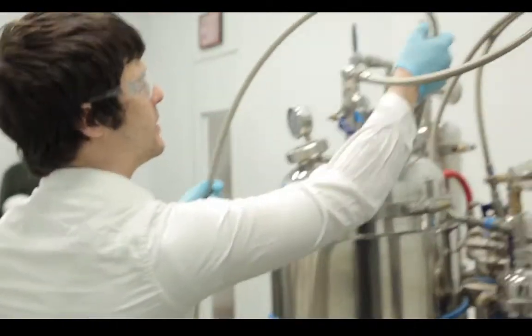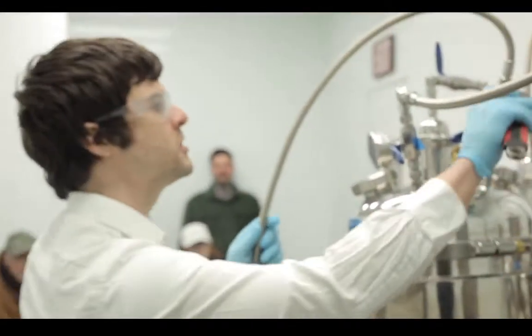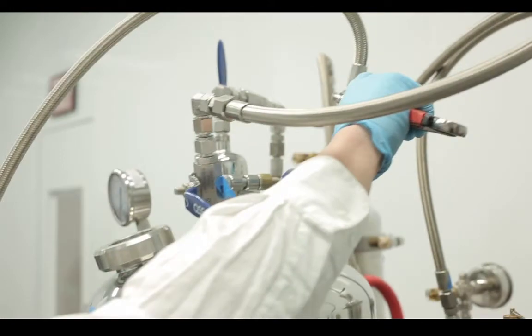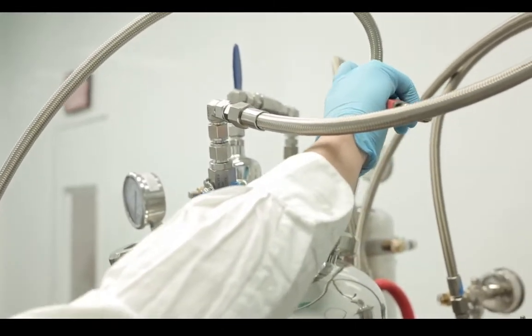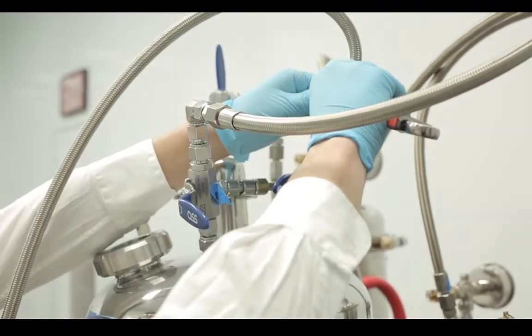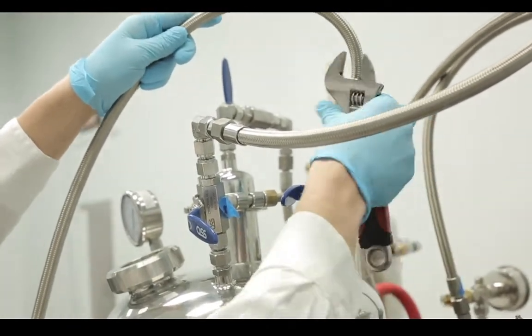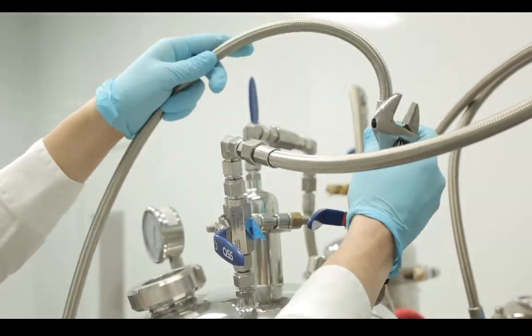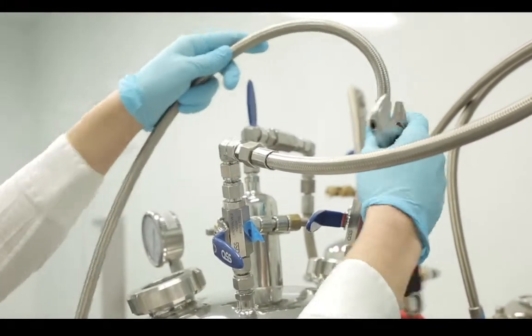Once we are finished with that, we will disconnect our vacuum hose and move it out of our way so that we don't have things clogging our working space. Safe housekeeping is what the construction industry calls that. The vacuum gauge can be finger tight, but I tightened it. So once again, if she's giving you trouble, a little wiggle goes a long way. Slide our vacuum out of the way.